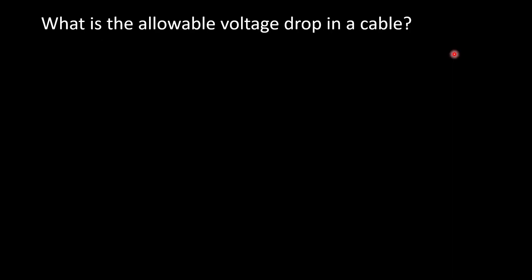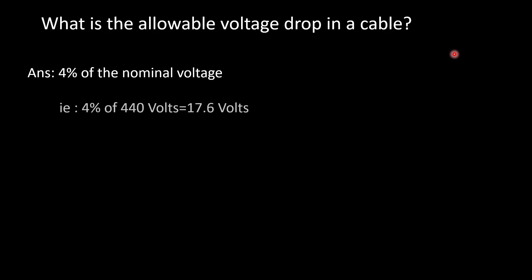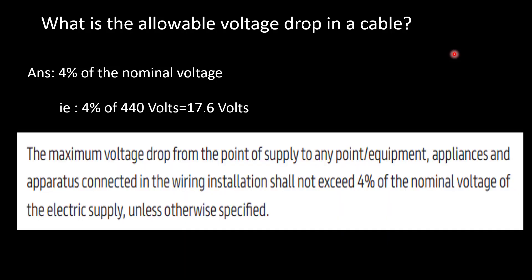What is the allowable voltage drop in a cable? The answer is 4% of the nominal voltage. For example, if the nominal voltage is 440V, then 4% of 440V equals 17.6 volts — that is the maximum allowable voltage drop. As per DEWA regulation: the maximum voltage drop from the point of supply to any point, equipment, appliance, or apparatus connected in the wiring installation shall not exceed 4% of the nominal voltage of the electric supply, unless otherwise specified.